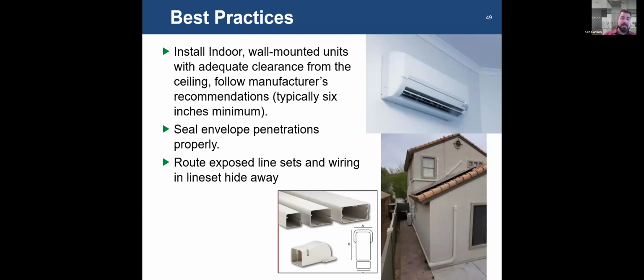Make sure you route your exposed line sets and wiring in a line set hideaway. So if you have your line set on exterior walls, as shown in the bottom right, the line set hideaway is a good way to basically hide your line set, hide your condensate line, and hide your power line. From the outdoor unit, these outdoor units typically power the indoor units. There's a wire that goes from the outdoor unit to the indoor unit, and that carries your power and communication wire. So everything gets put into a line set hideaway. It comes in pieces. It's two-piece. You can mount the bottom piece right to the wall, run it all the way from end to end.